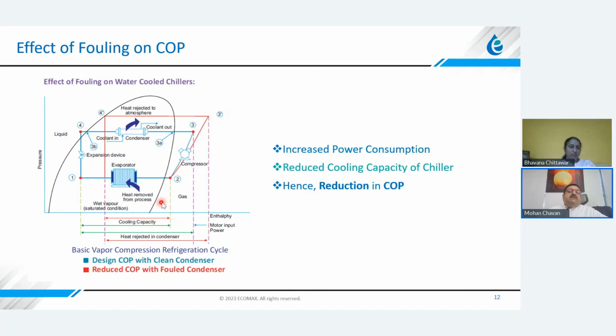Simultaneously, as the compressor pressure has increased, the compressor will draw more power from 3 to 3 dash, right? So you might have, let's say, 100 kilowatt here, and 3 dash could be, let's say, 120 kilowatt. So in short, your power consumption has gone up and your cooling capacity has gone down. And therefore, there is a reduction in the COP, that is coefficient of performance. That means your IKW per TR has gone up.